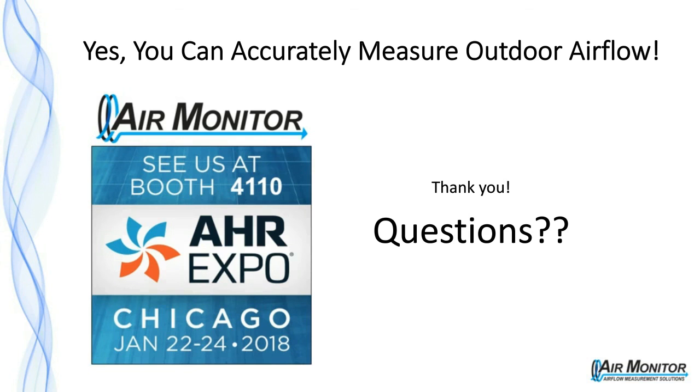Okay, the last question: how difficult is it to install the probe in a bird screen on a typical RTU? Not very difficult at all. You need access to the outside of the bird screen. We're talking about installing probably 3 or 4 screws, and then tubing from the sensor, which is going to be on the outside of the bird screen, facing the sensor, and then that goes back to the electronics panel. That is provided that the bird screen will give us the pressure drop required. If it doesn't, it can be replaced with a piece of expanded metal.